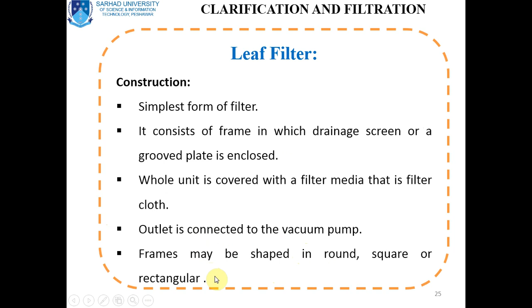It consists of a frame in which a drainage screen or grooved plate is enclosed. The whole unit is covered with filter media, that is a filter cloth. You can see that is the filter cloth. The whole unit is surrounded by the filter medium, that is filter cloth. The outlet is connected to the vacuum pump. The frame may be shaped round, square or rectangular.